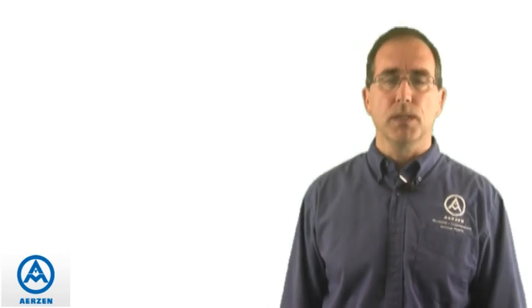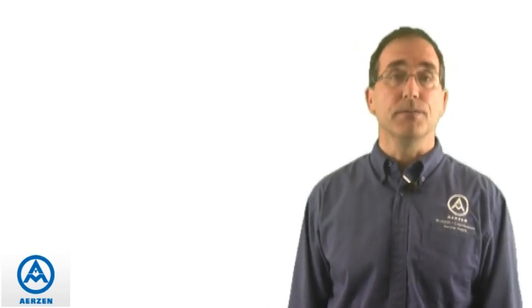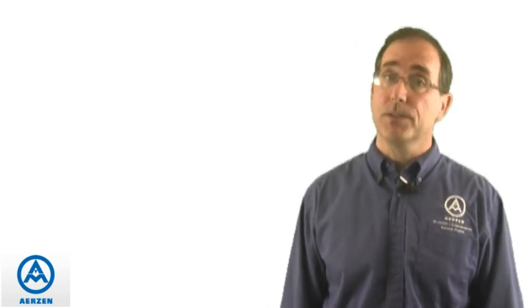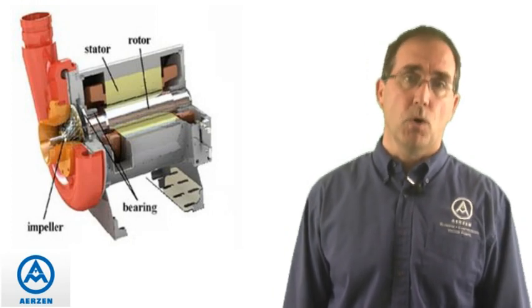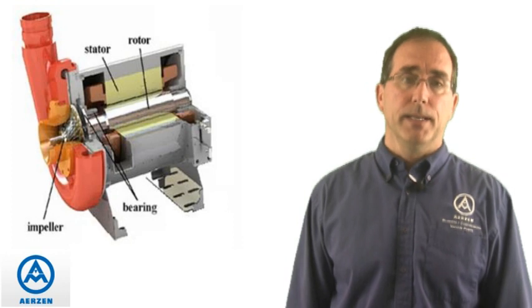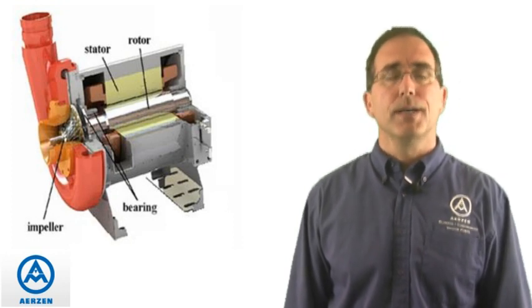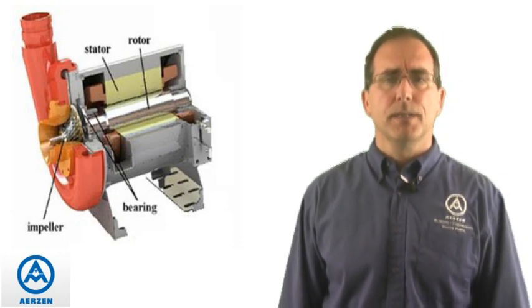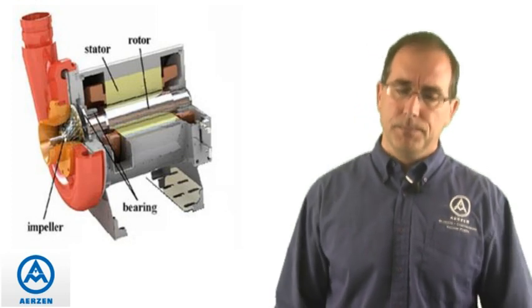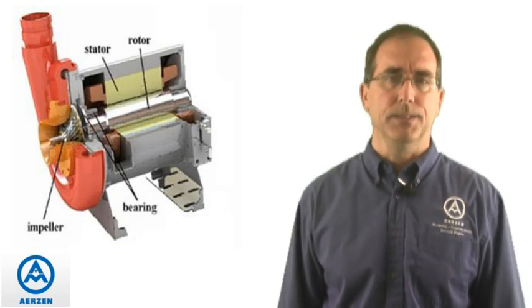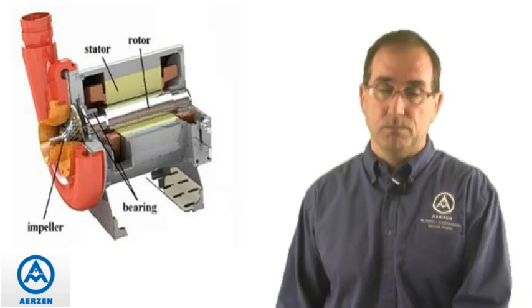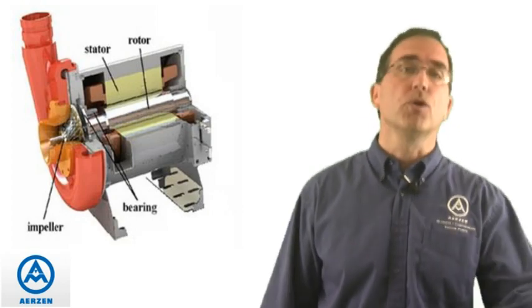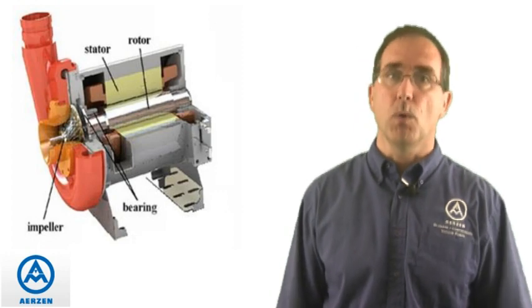The centrifugal blower technology gradually evolved to the high-speed turbo blower, which is probably the newest player in wastewater. It incorporates airfoil bearings, permanent magnet motor, and an onboard motor control system. The whole unit is self-contained, with sizes ranging from as low as 50 horsepower all the way up to 400 horsepower or even more.